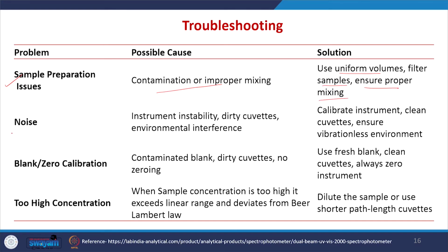And if you are facing a problem like noise, that may be due to the instrument instability, or it may be due to the cuvette which is not clean, or it may be due to environmental interference. So, calibrate the instrument, clean the cuvettes, and make sure that there is a vibrationless environment. And if you are facing a problem in the blank or zero calibration, the possible cause may be due to a contaminated blank, or the cuvette is not clean, or there is no zeroing. So, always use a fresh blank, clean the cuvettes as I told earlier in the previous slides also. So, always zero the instrument.